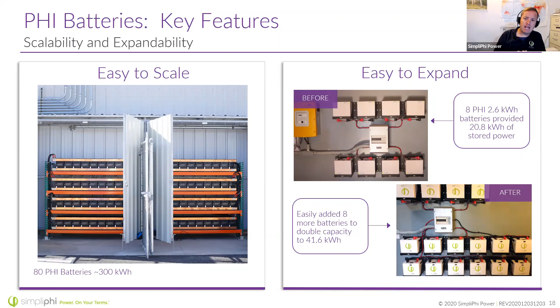Here's an example. We came back to a house with 8 batteries. We came back and added 8 more batteries, kept that same existing combiner, kept that same SMA Sunny Island there. The picture on the left here is a great example of what it looks like to scale up a system. I love this picture because of all of the copper bus bars you see. This is 80 batteries that we scaled up to provide 300 kilowatt hours. This is at an airport hangar out in Hawaii.